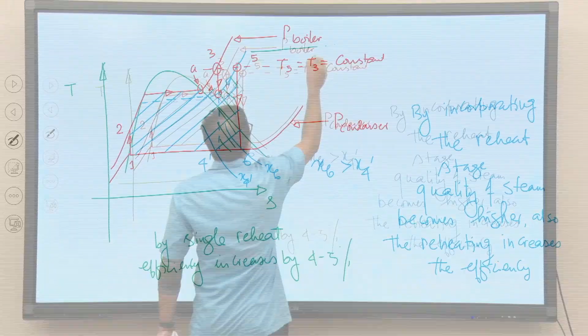So, you can say that we can increase the number of reheat stages to more than 1. Again let me talk about it. So, see what is done, let me tell you. Boiler is operating at high boiler pressure. Steam is superheated up to point 3, beyond point A. Steam is taken to the high pressure stage turbine and it is allowed to expand up to an intermediate pressure, that is P5. So, this is the intermediate pressure.